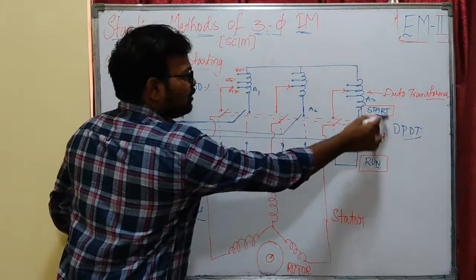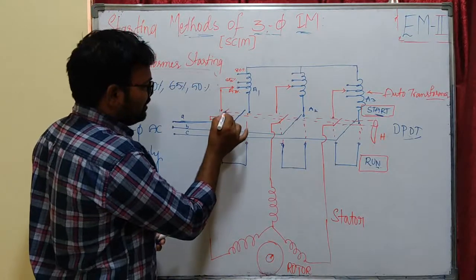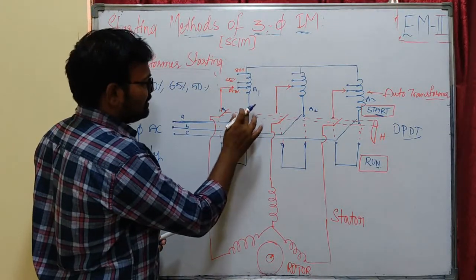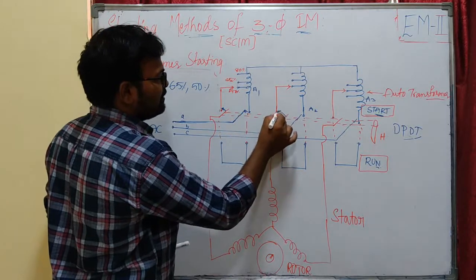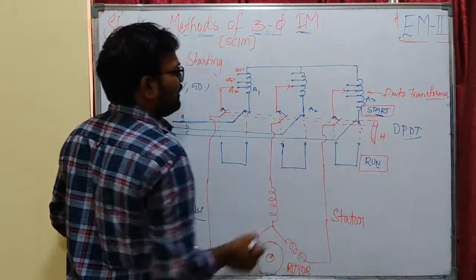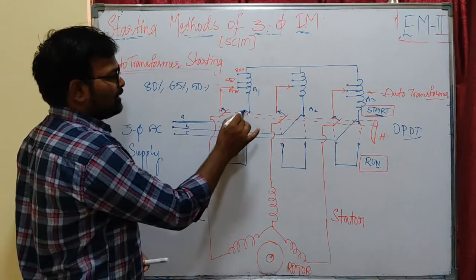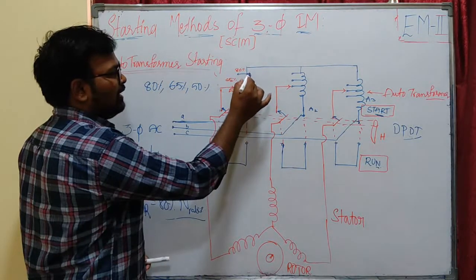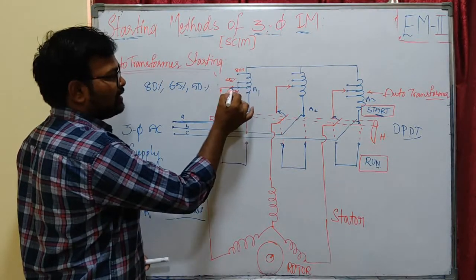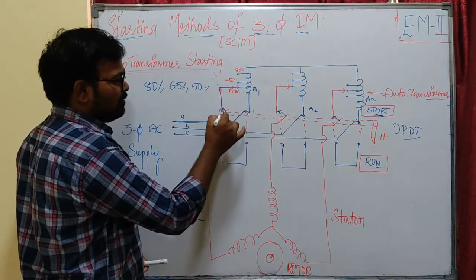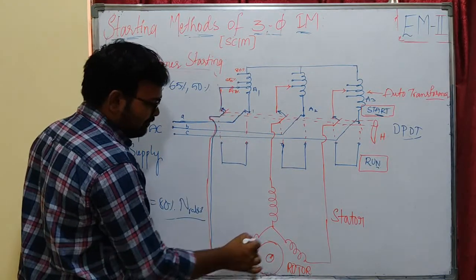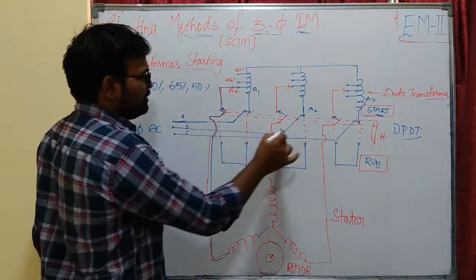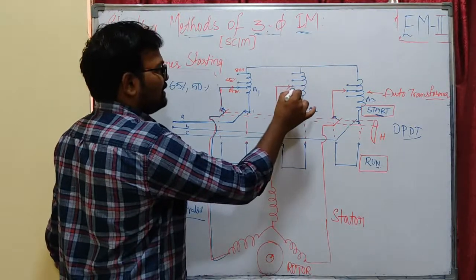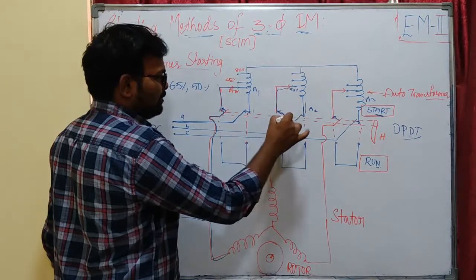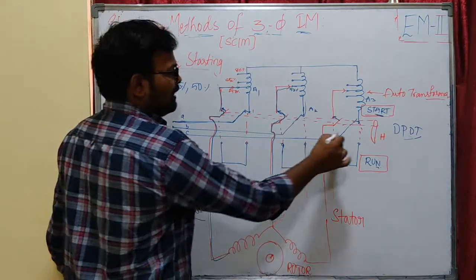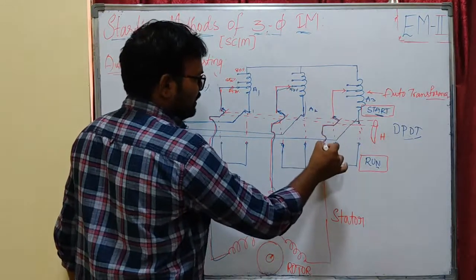When this is in the start position, our switches will be connected to this. This will be connected to this. So you can see our A phase is connected to auto transformer terminal 1, and the second terminal, the auto transformer secondary terminal, is connected through this winding, and this will be connected to our stator of our induction machine. You can see the B phase is also connected to the auto transformer, and here it is a tapping percentage. This will be connected to our stator winding. Like this, our third winding is also connected to our stator winding.